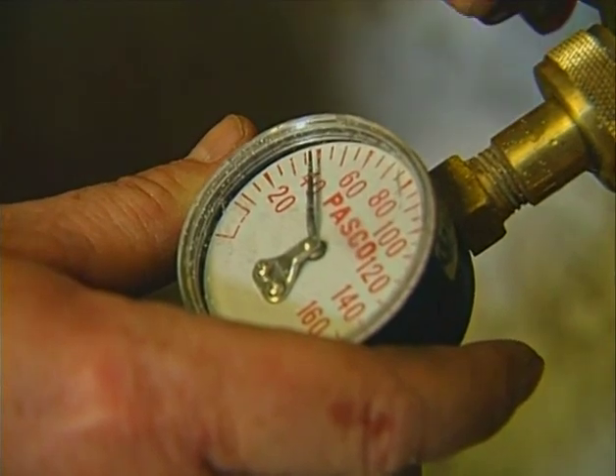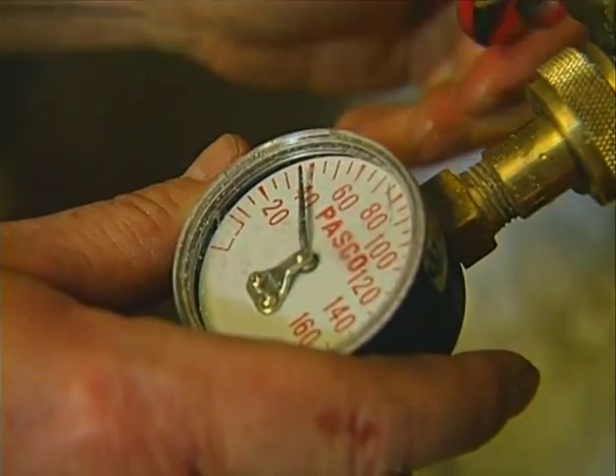Checking the pressure, we were looking at about 35 to 40 pounds of pressure. So the pressure looked rather low. Also then in contact with the water authorities, we weren't going to be allowed to tie into the existing water line. We would actually have to bring in another water line from the street. So at that point, we looked at the alternative of providing a tank and a pump. So that's what this is all about over here.